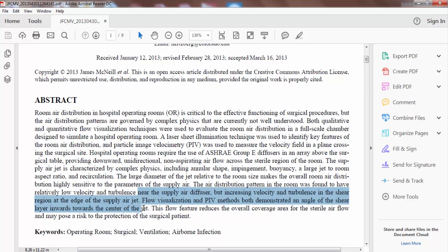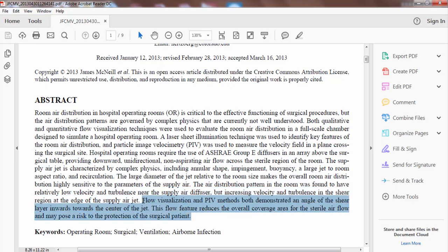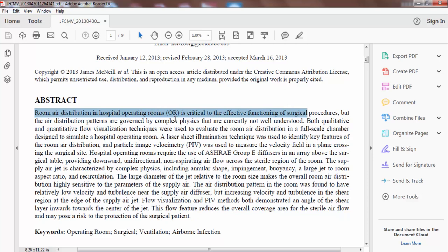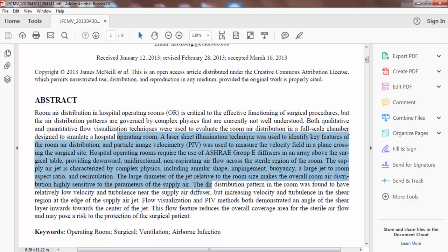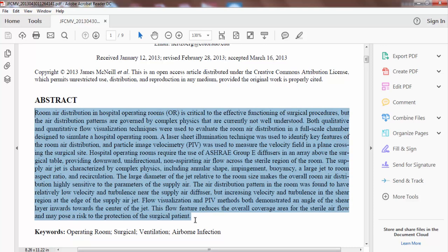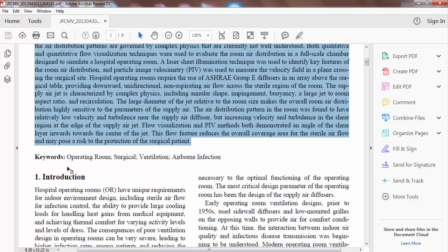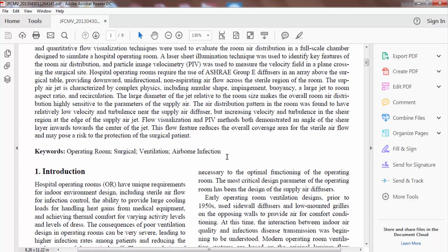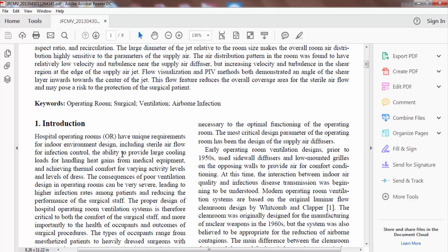'The air distribution pattern in the room was found to have relatively low velocity and turbulence near the supply air diffuser, but increasing velocity and turbulence in the shear region at the edge of the supply air jet.' Flow visualization and PIV methods both demonstrated an angle of the shear layer inward toward the center of the jet. This flow feature reduces the overall coverage area for sterile airflow and may pose a risk to the protection of the surgical patient. Notice the coherence and clarity throughout the abstract.